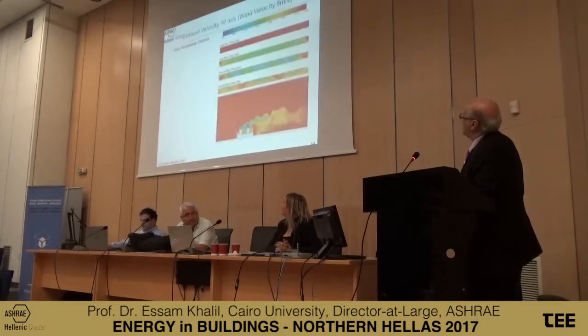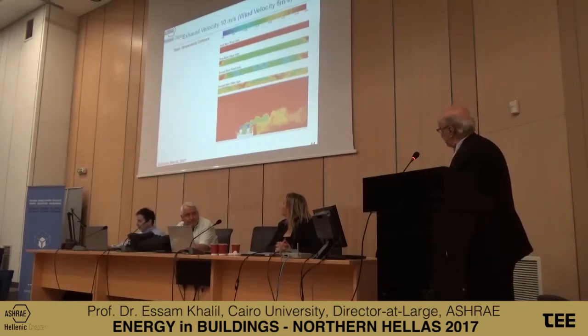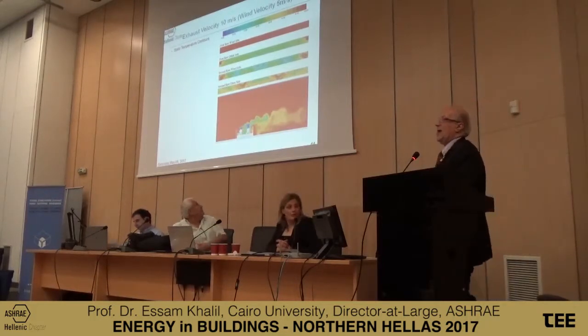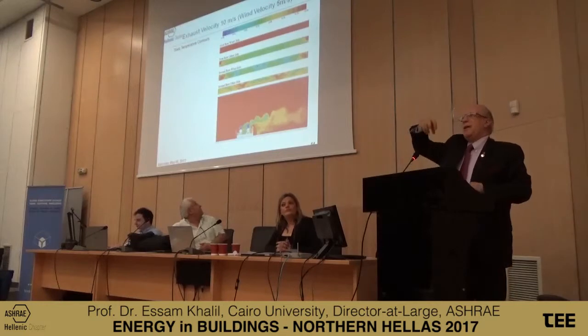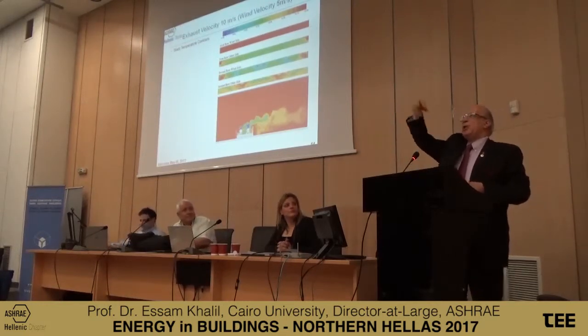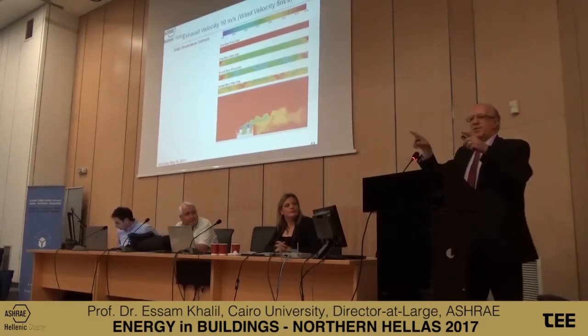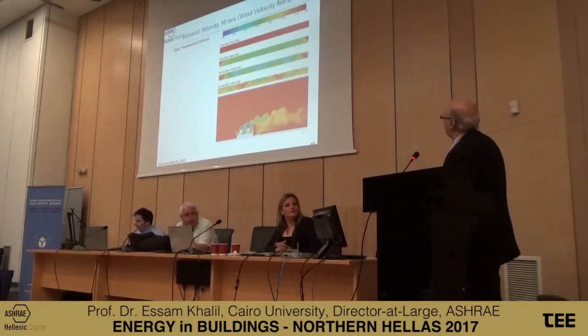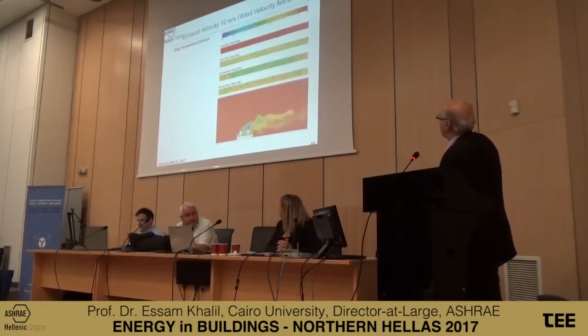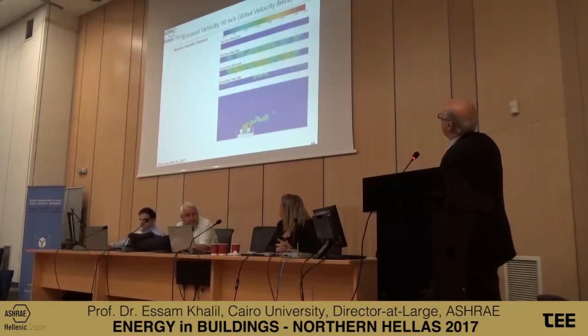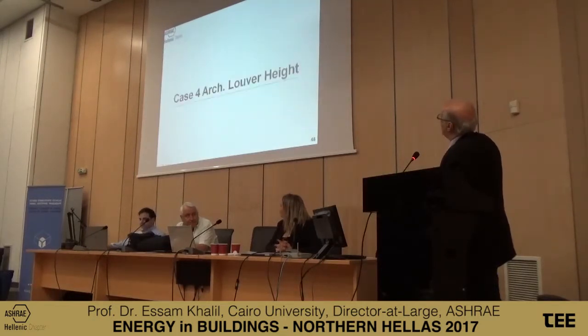Also the exhaust velocity. And here you have the interaction between the two cells. As you can see, this area is where we have circulation, which is not good, because we'd like the air that has been saturated with water vapor to go away, not to be recirculated in the middle. So here we have the humidity at various exhaust velocities.